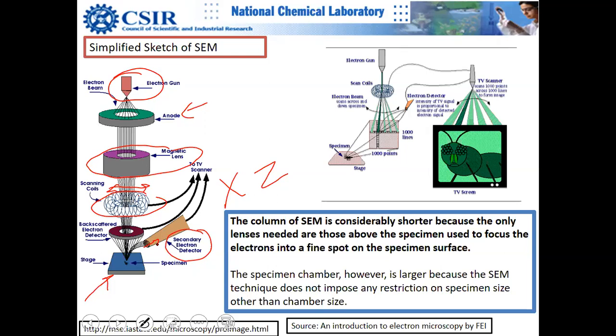In TEM, the image has contrast contributions from three sources: Z contrast (which is very strong), thickness, and crystallinity contrast. None of these three contrasts exist in secondary electron SEM imaging. The only origin of secondary electron contrast is topography — that is the only contributing factor, which also makes things simpler.